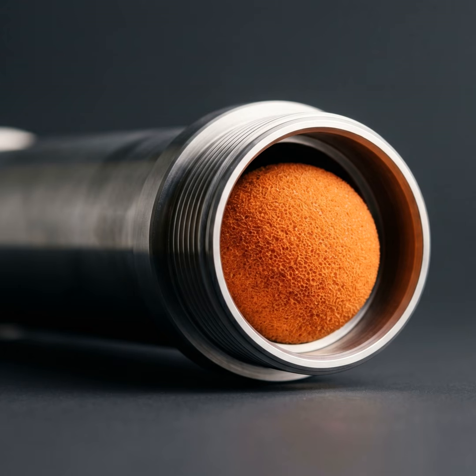And what does the trap do? The trap has a specialized screen that allows the water to pass through unimpeded. So the building gets its chilled water without any flow restriction. But it catches the oversized neoprene balls. The balls are corralled, held in a collector, and then automatically prepped for the next cycle. And how often does this cycle happen? Every 30 minutes. Yeah. So it is a state of constant, gentle, physical friction. It never stops. Never. The scale literally cannot form because the microscopic foundation is being wiped clean twice an hour.